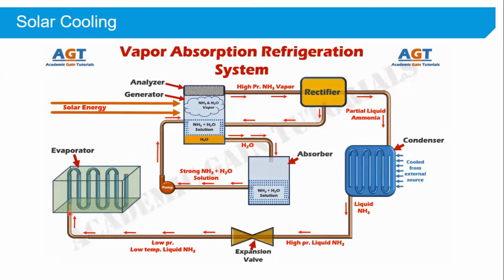We all know that the main cooling effect or refrigeration effect always occurs in the evaporator. So, when this low pressure, very cold, chilled, low temperature liquid ammonia will enter the evaporator coils, it will absorb all the heat present in the surface of the evaporator coils. By absorbing all the heat from the surrounding surface of the evaporator coils, this cold chilled liquid ammonia will turn into low pressure ammonia vapor inside these coils, and the surrounding surface of the evaporator will become cold by losing the heat to this liquid. Thus the cooling effect or refrigeration effect has occurred in the evaporator. After that, this low pressure ammonia vapor will leave the evaporator and enter the absorber again through this connecting pipe.